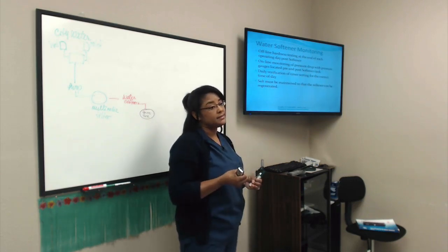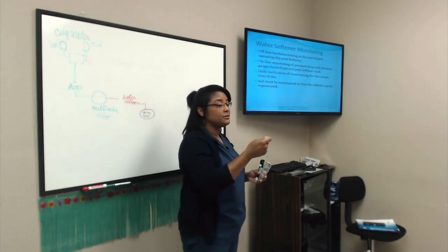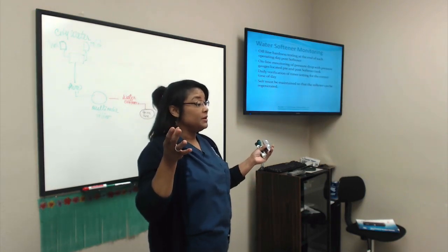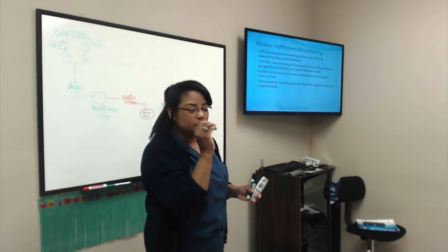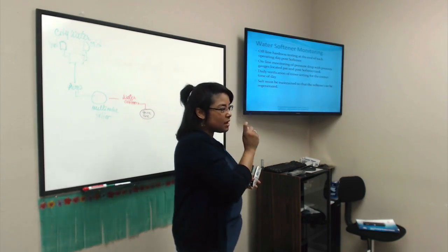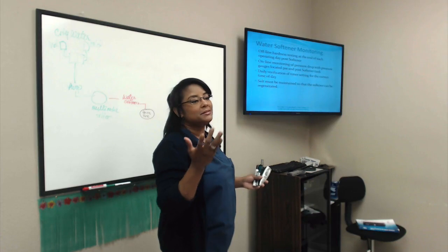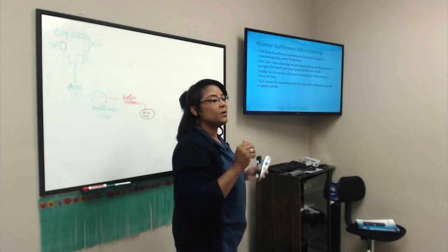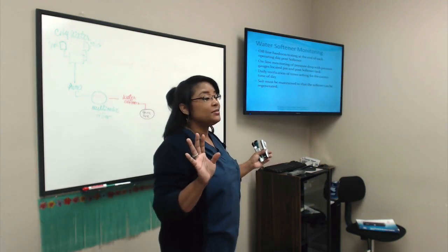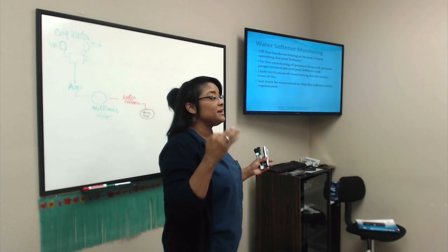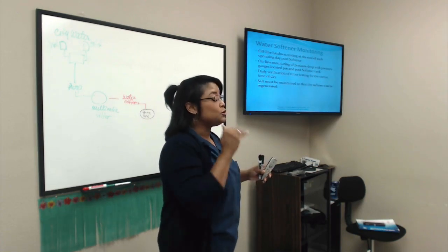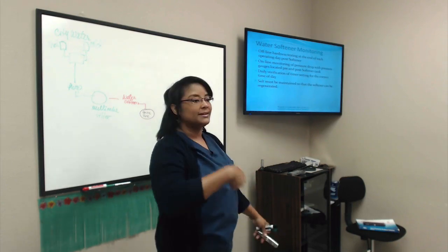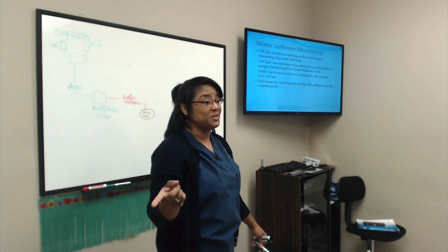The reason for that is because the softener is going to be set to do the regeneration during nighttime while the patients are not there. So if the time on that softener is not accurate, and let's say we lost power and nobody fixed it, and it's showing you that it's 1 a.m., and the regeneration is supposed to be at 3 a.m. So 2 hours into dialysis, the thing is going to start regenerating itself while we're dialyzing patients.